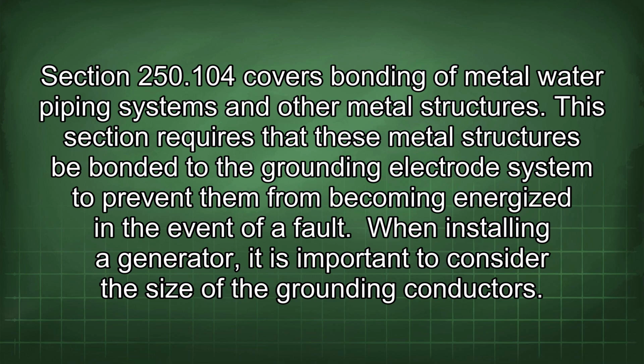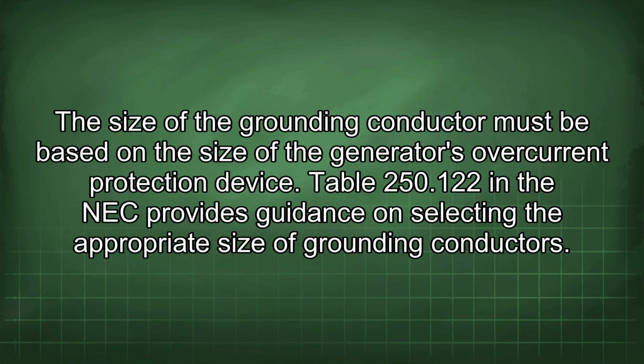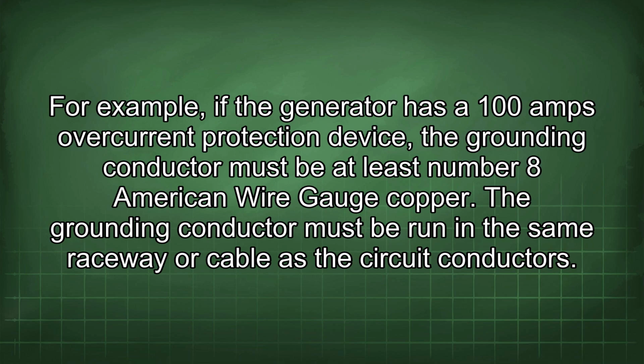When installing a generator, it is important to consider the size of the grounding conductors. The size of the grounding conductor must be based on the size of the generator's overcurrent protection device. Table 250.122 in the NEC provides guidance on selecting the appropriate size of grounding conductors. For example, if the generator has a 100 amps overcurrent protection device, the grounding conductor must be at least number 8 American wire gauge copper. The grounding conductor must be run in the same raceway or cable as the circuit conductors.